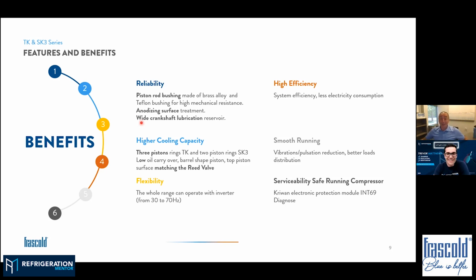This is the reason why you can see a lot of features that the standard compressor doesn't have, like particular finishing on the piston rods, on the bushings, and also the finishing of the surfaces of the crankshaft, which are crazy compared to other compressors that work for lower pressure. You can imagine how important it is to have a super finished surface when those pressure differences are involved, and every single scratch can be the start of a crack. So you need to pay particular attention to that.